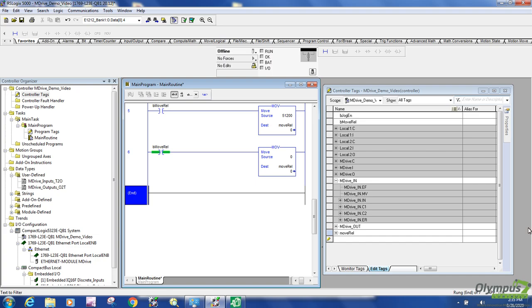Okay, since we have the motor set to closed loop mode, which is what we did in the first video, and we have the run current set as well to a low enough percentage so I can grab it by hand and stall the motor. In this video, we will go over how to recover from a locked rotor fault.